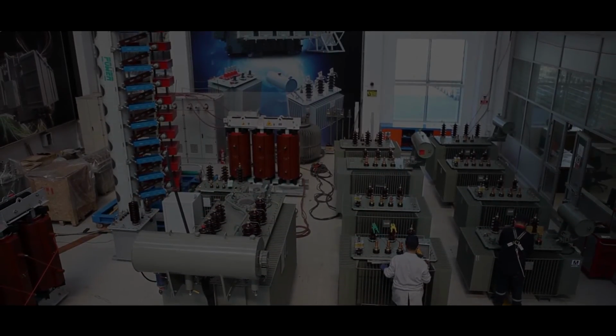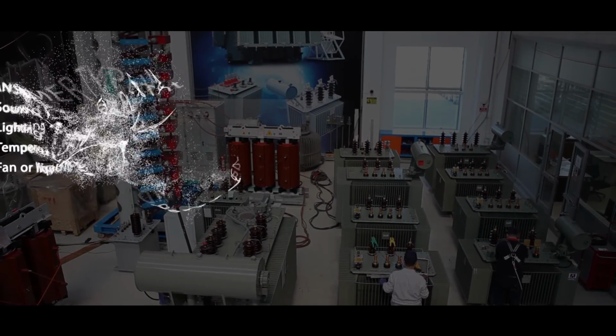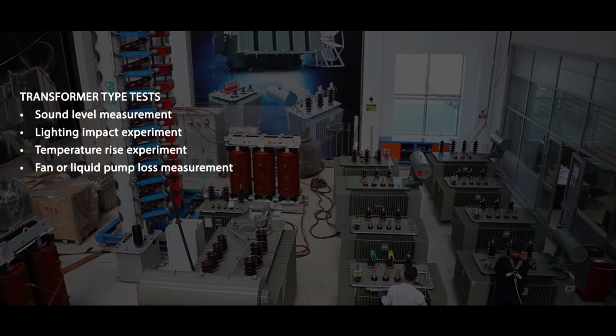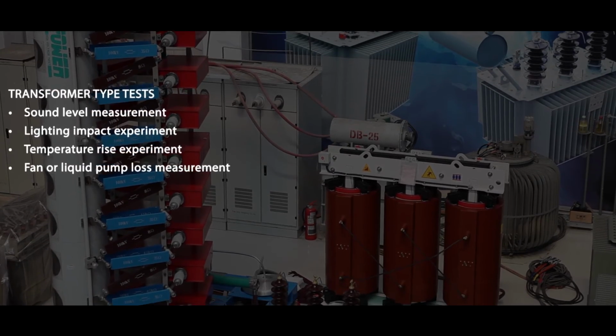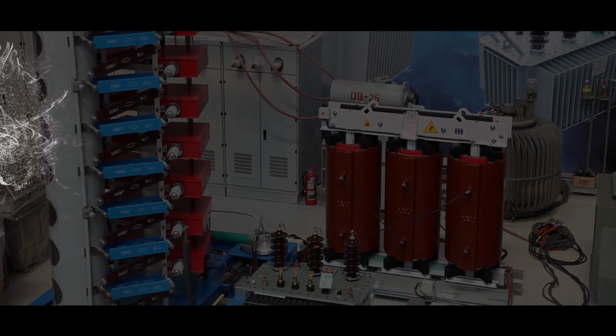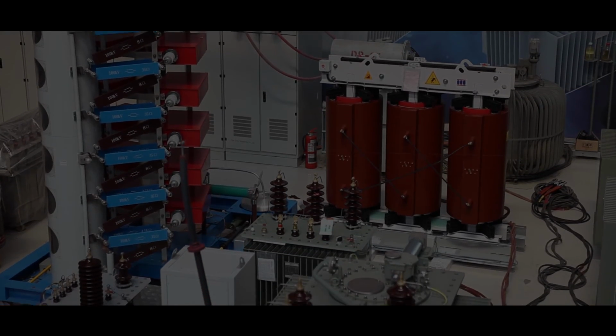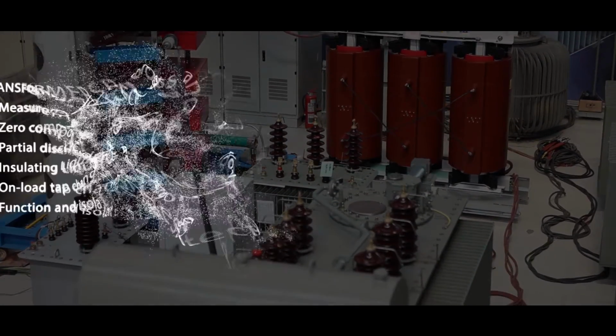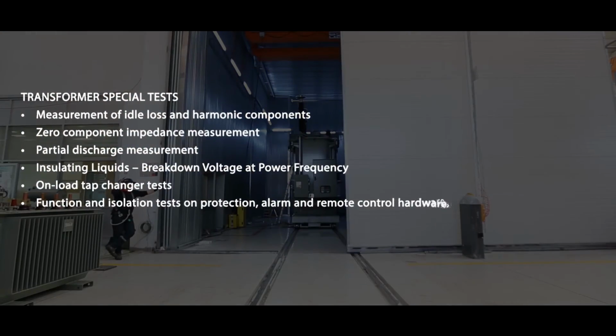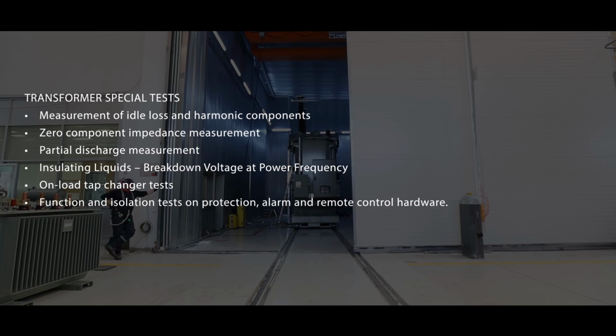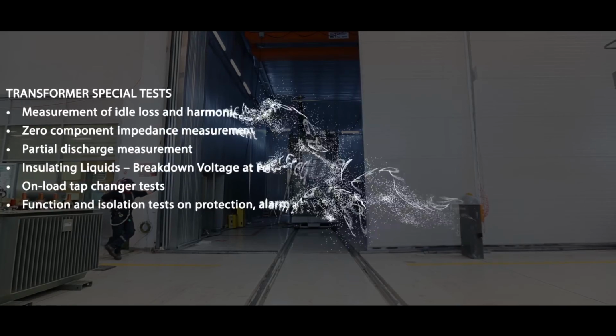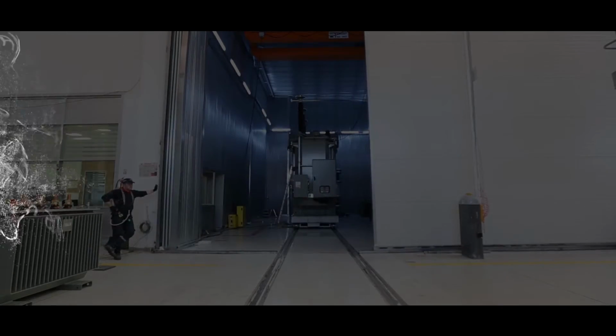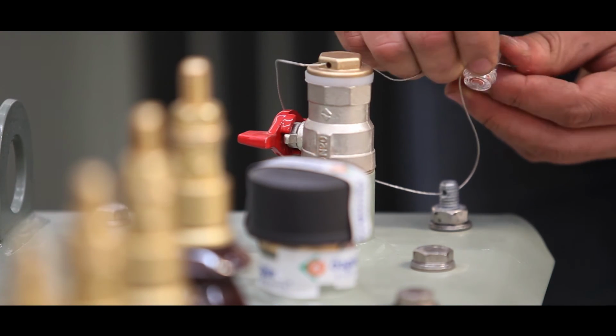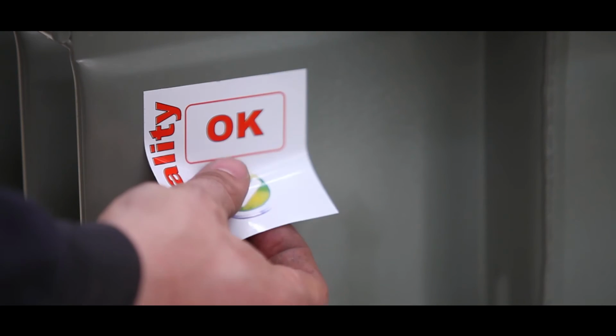Transformer type tests. The following tests are also applied to the same type transformers if requested by our customers. Sound level measurement, lightning impact experiment, temperature rise experiment, fan or liquid pump loss measurement if a fan cooling or liquid pump system exists. Transformer special tests. Apart from the services mentioned, the following tasks can also be performed if requested by our customers. Measurement of idle loss and harmonic components. Zero component impedance measurement. Partial discharge measurement. Insulating liquids. Breakdown voltage at power frequency. On-load tap changer tests. Function and isolation tests on protection, alarm, and remote control hardware.